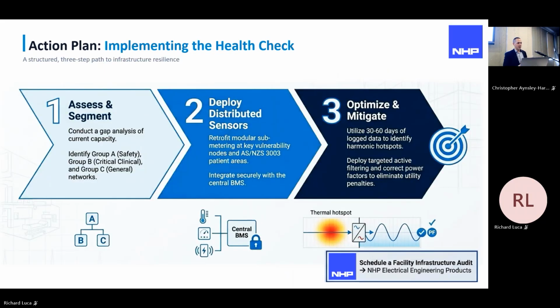So a quick 3-step action plan is: assess, segment the loads into groups, critical, to perform your gap analysis, and then distribute the sensors in those locations and put it all back to the gateways and back to the network. But that's not enough. We need to look at the data, optimize, and then mitigate. So if there's a hotspot in the system, we need to be trending that, set alarms, notifications, because that could mean later down the track that there's some unplanned outage.